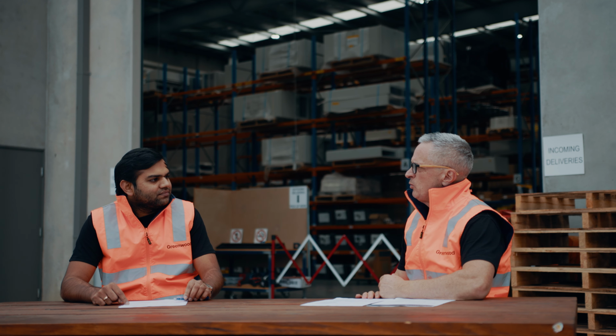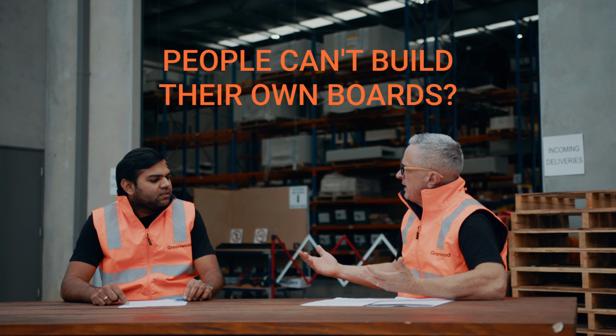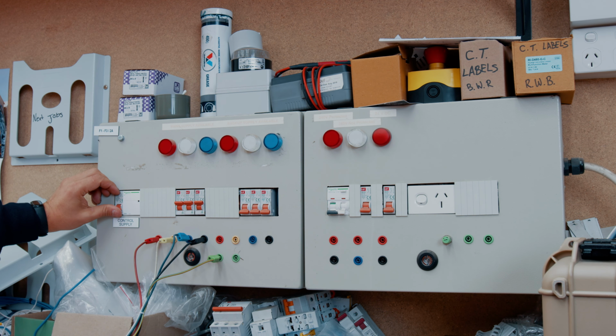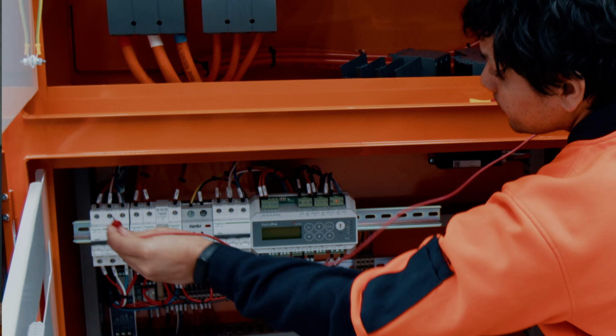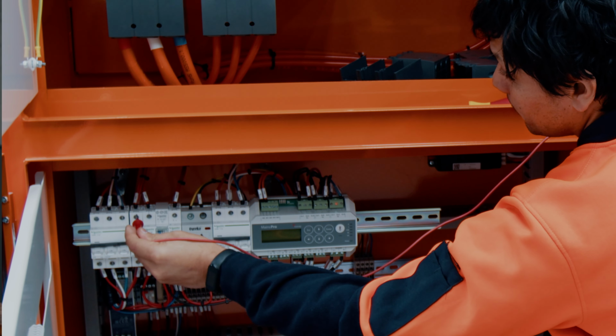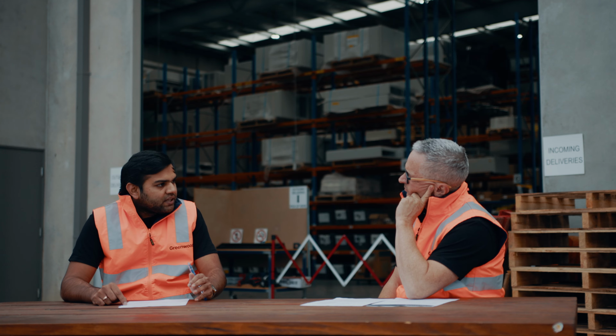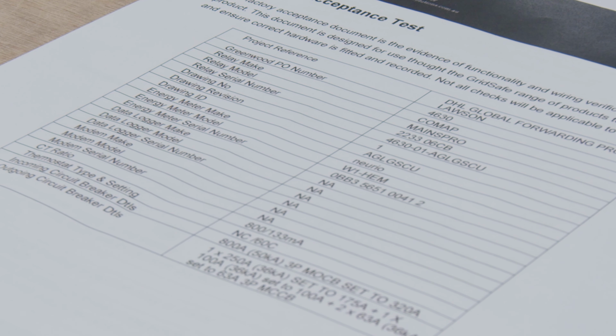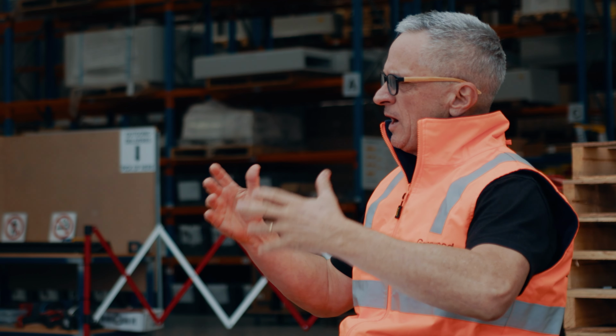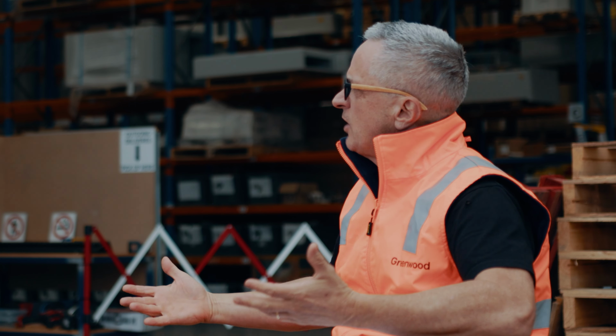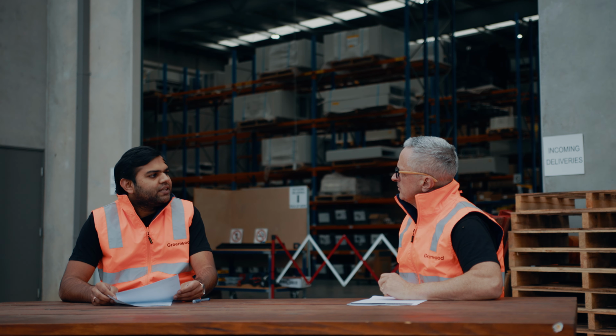Electricians are very practical people. Why can't they build their own interface protection board? What happens to the type testing of that board? And also, most of the time, the end customer would ask for the specific requirements, and if the board is built by themselves, they need to do all these documentations by themselves. With the type testing, surely you need specialised facilities to type test. Yeah, definitely they do need a specialized facility to type test the enclosure, and there are multiple factors which are looked into in the type testing. I think it is around a 13-point checklist or something like that.